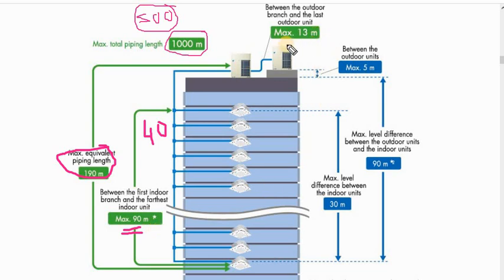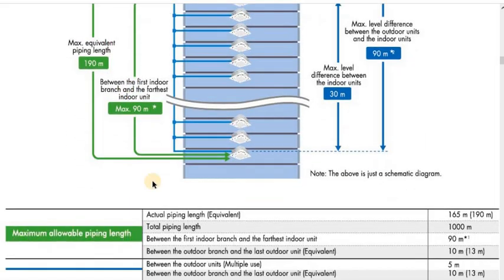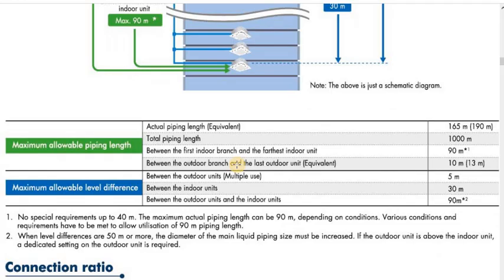The next one is 13 meters. From this outdoor to this outdoor, it should not be more than 13 meters between the outdoor branch and the last outdoor unit. Okay friends, these are the basic limitations you have to follow. Maximum level between the indoor units is 30 meters. The maximum level should not be more than 30 meters. If it is more than that, you have to break the system. These are the first few limitations while designing our Daikin VRV system.